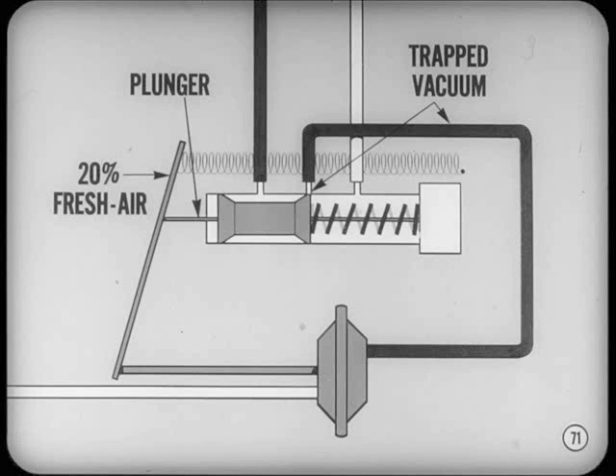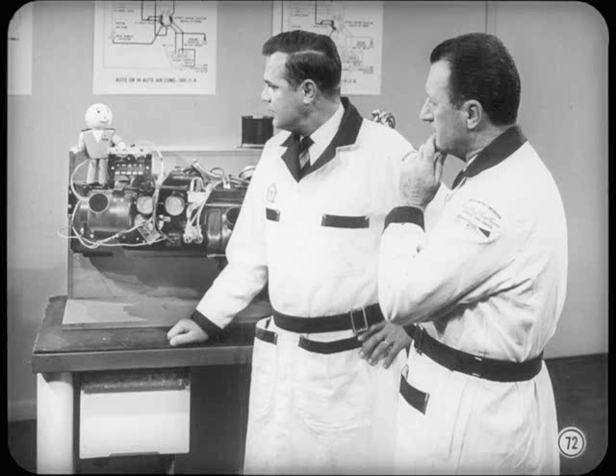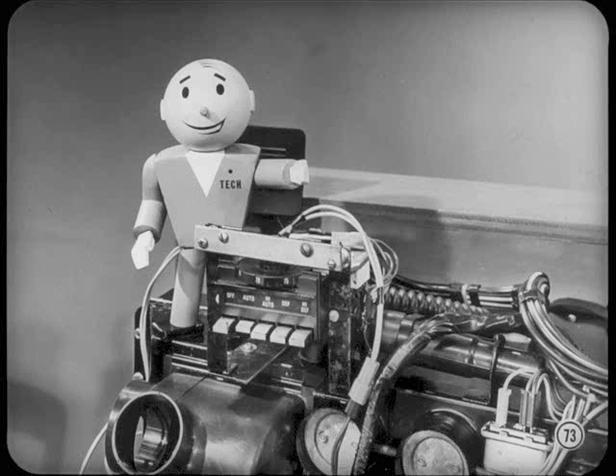Plunger movement allows a valve in the transfer switch to cut off the vacuum circuit to the vacuum actuator when the fresh air door reaches the 20% fresh air position. Trapped vacuum holds the door in this position. This door position is used only for maximum cooling. Now, we could go on and explain what happens in the slave circuit for every push-button position and for every heating or cooling requirement. That would take a lot of time, and you couldn't possibly remember all the combinations anyway. Instead, I think we better spend the remaining time covering the blower circuit units that we haven't talked about yet, so you'll know what they are and what they do.